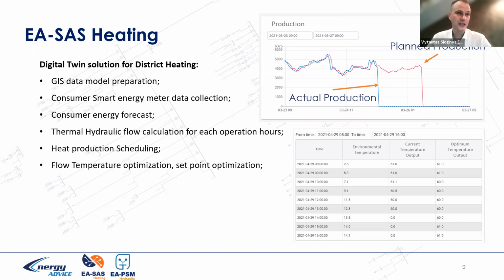When we came to the district heating company, we found that the supply temperature to the network was lowest 70 degrees and highest probably 95. So it was like a third generation district heating company. But when we started to optimize operation through digital twin and calculation each hour, and providing set points for operation, we optimized district heating supply temperatures to a summertime average of 60 degrees, and for 90% of hours per year the highest was near 70 degrees, probably a couple of degrees more than 70. So we utilized the existing infrastructure to run the district heating company as a fourth generation, in fact with only one investment, in digitalization.